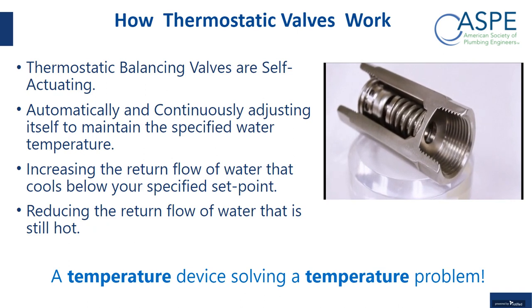And so the video we're showing here on the right is a basic thermostatic balancing valve that's at a fixed temperature, not an adjustable temperature. What my yellow cursor is pointing to, hopefully you can see my cursor, is the paraffin wax actuator, the cup where the wax is stored. Now this video is sped up. It's showing the valve moving a lot quicker than it would in real life. But what you'll see here on the right where I'm pointing is an orifice, and this that you see extending into the orifice is the plug.